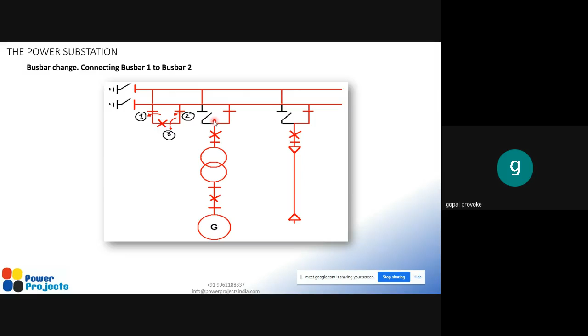So from the energized red color bus bar, the supply will be transmitted to the other bus bar. So now this bus bar is also energized, and now we can close the other two isolators also. By closing these isolators, we are having two parallel paths from generator to load.